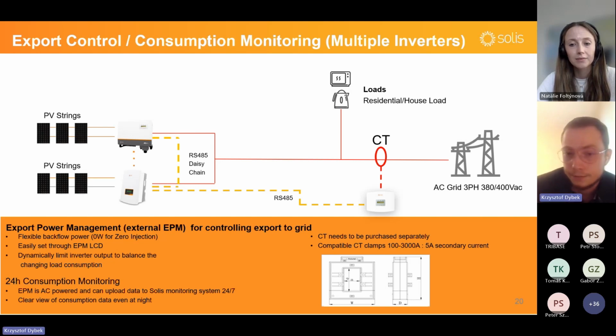So in other words, to determine the correct current transformer rating, multiply the full load amperes by a factor of 1.25. This is allowing sufficient headroom to also read overload conditions. Range for CTs for this EPM is between 100 and 3000 amps. Secondary current needs to be always 5.